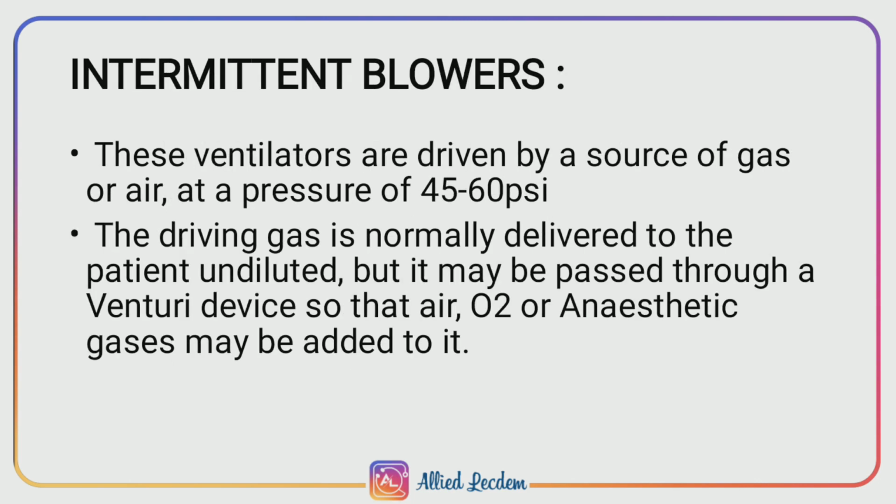Intermittent blowers. These ventilators are driven by a source of gas or air at a pressure of 45 to 60 psi. The driving gas is normally delivered to the patient undiluted, but it may also be passed through a Venturi device so that air, O2, or anesthetic gas may be added to it.